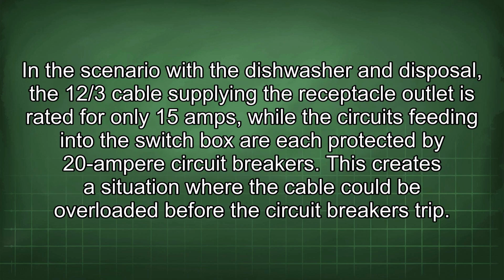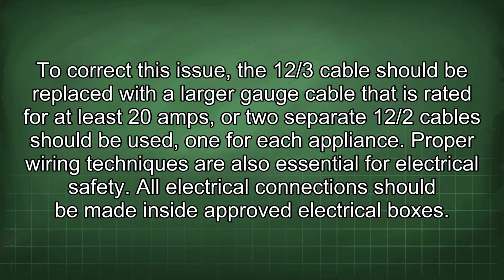In a scenario with a dishwasher and disposal, the 12/3 cable supplying the receptacle outlet is rated for only 15 amps, while the circuits feeding into the switch box are each protected by 20 ampere circuit breakers. This creates a situation where the cable could be overloaded before the circuit breakers trip. To correct this issue, the 12/3 cable should be replaced with a larger gauge cable that is rated for at least 20 amps, or two separate 12/2 cables should be used, one for each appliance.